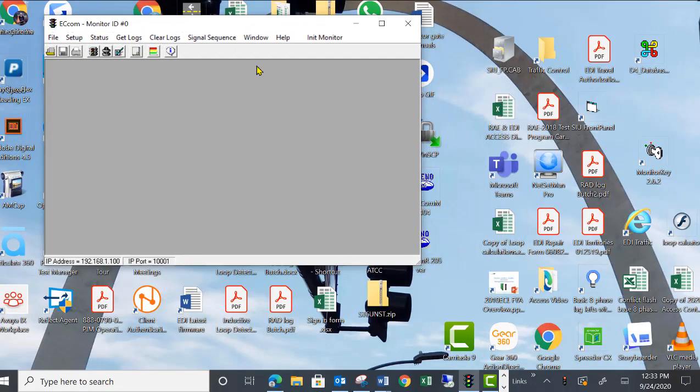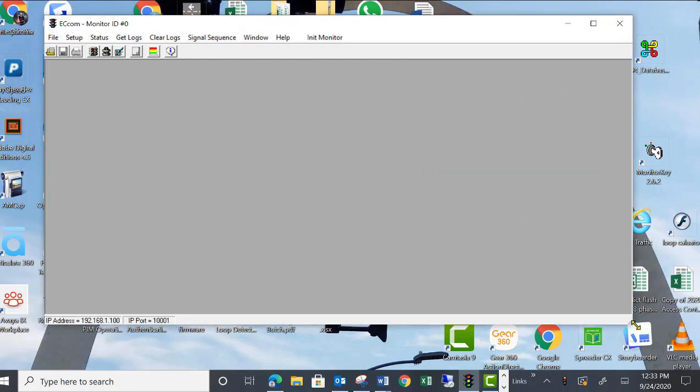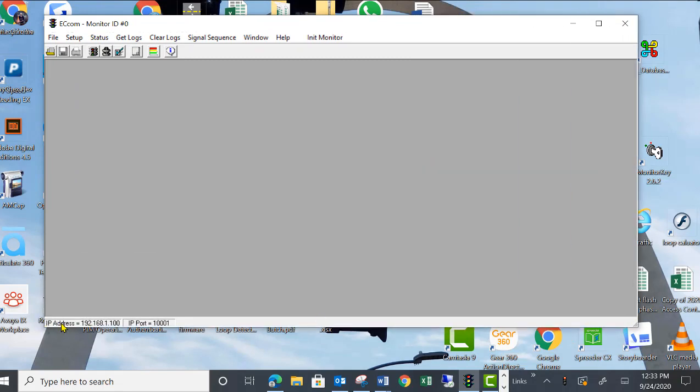Some of the things I want to show you when you have the software open: down here it tells you how you're communicating, or the last time you talked to a monitor. You used the IP or LAN connection, which is an RJ45 or Ethernet connection, and it was 192.168.1.100, which is our factory setting, and the IP port is also down here. If you open up your software and it's already illuminated, meaning these aren't grayed out, then you are talking to the unit.